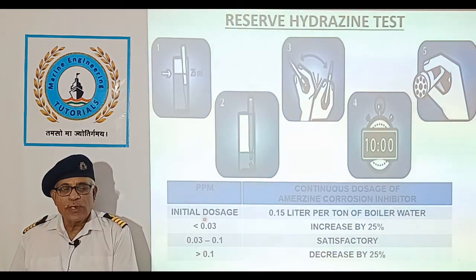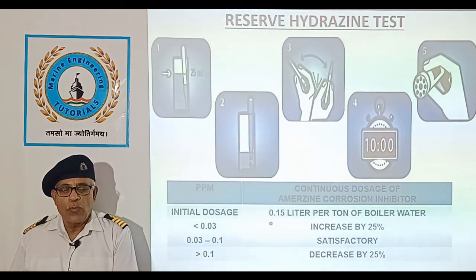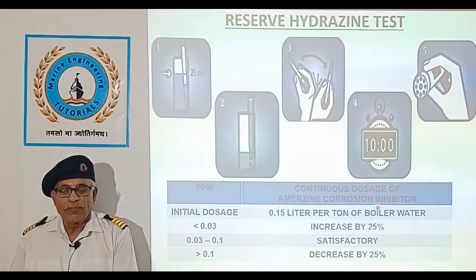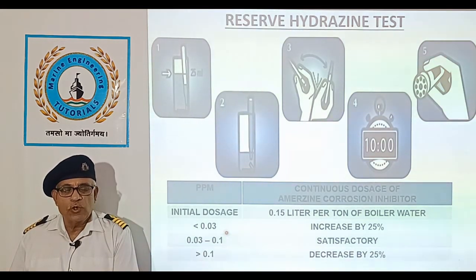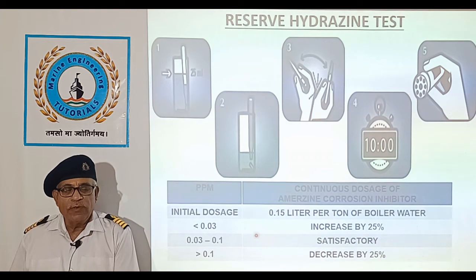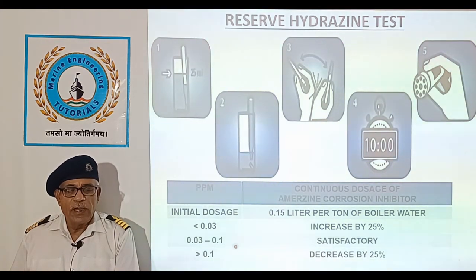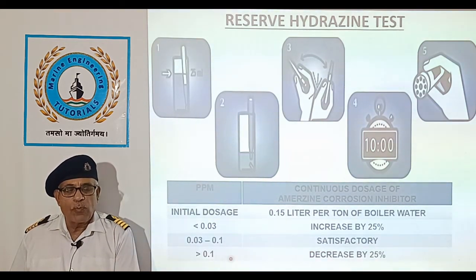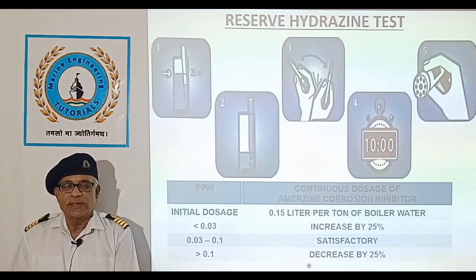Initial dosage of hydrazine is 0.15 litre per ton of water of the corrosion inhibitor. If the ppm is less than 0.03, we need to increase the dosage by 25%. If the ppm is between 0.03 to 0.1, it is the satisfactory range. In case the ppm goes beyond 0.1, we need to decrease the dosage by 25%.